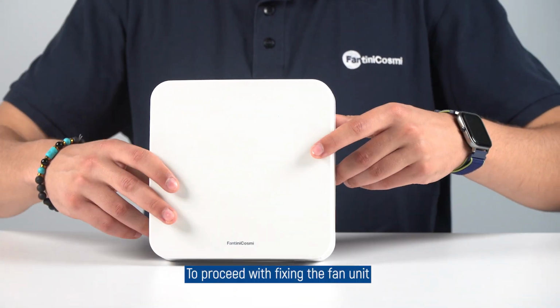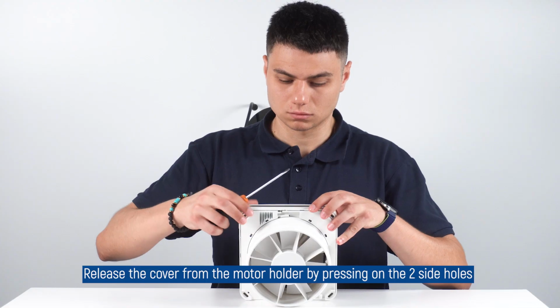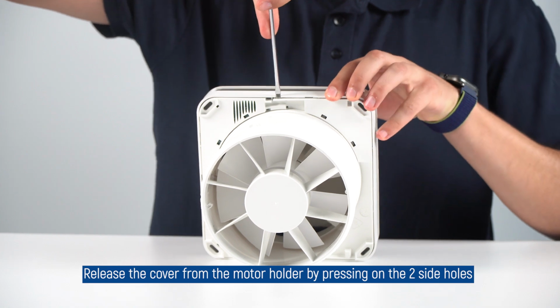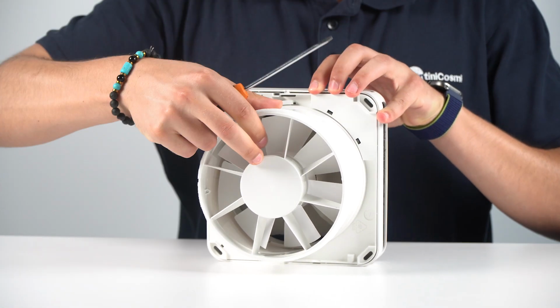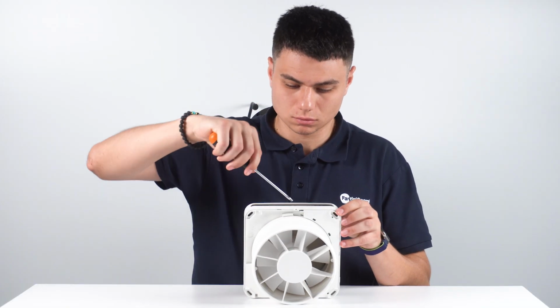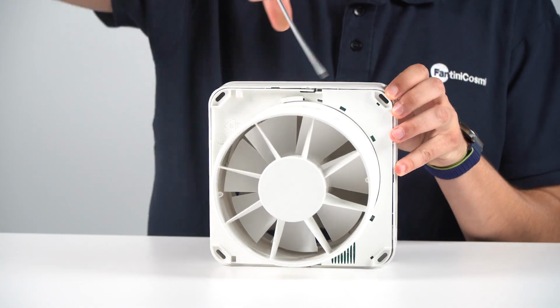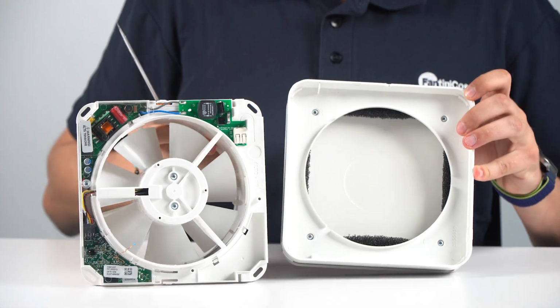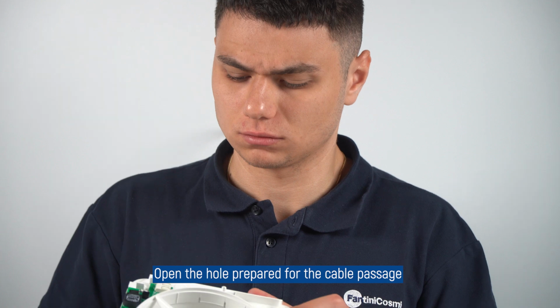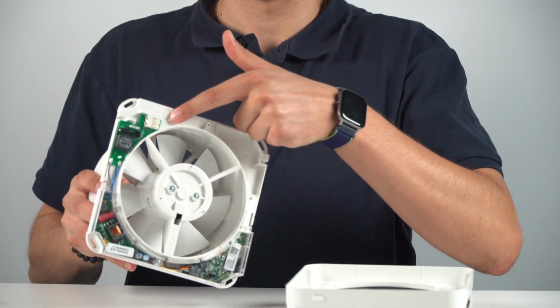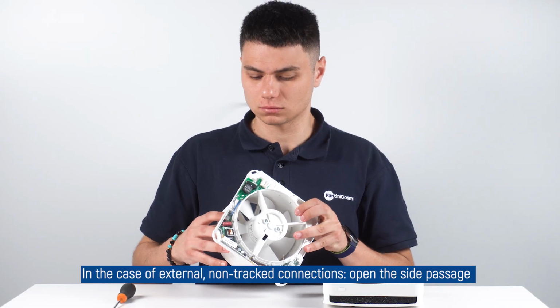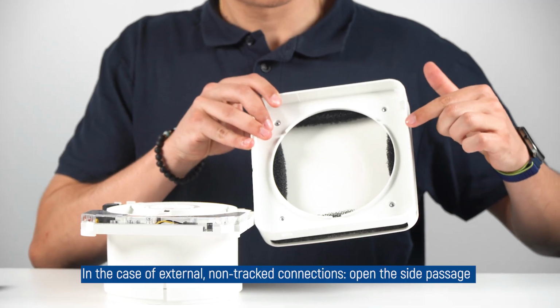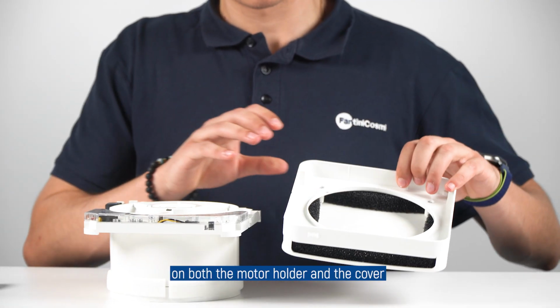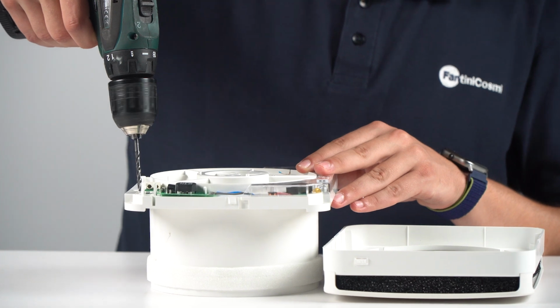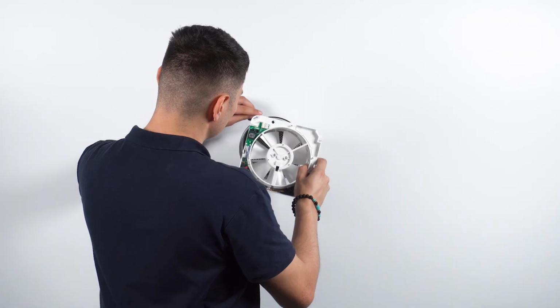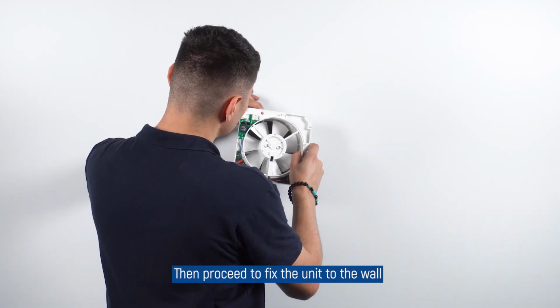To proceed with fixing the fan unit, release the cover from the motor holder by pressing on the two side holes. Open the hole prepared for the cable passage. In the case of external non-tracked connections, open the side passage on both the motor holder and the cover. Then proceed to fix the unit to the wall.